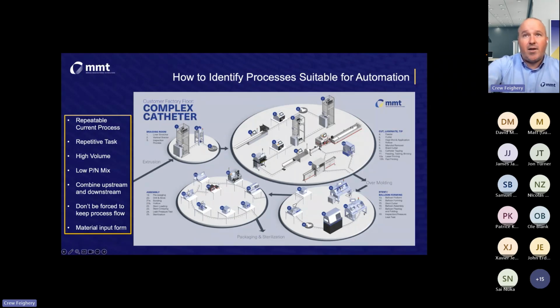You need to remove the mandrels, so you're going to pull those out. You're going to cut that braided catheter to length. Now you need to bond on the soft tip with an RF bonding system. And then once you've done that, you really would like to test the jacket to make sure that you don't have any exposed braids, whether when you do the reflow process it squeezed down too hard and left a thin spot in the Pebax jacket and then caused an exposed braid, or in the area where the bond goes from braided to non-braided, to make sure that one of those wires didn't flare out on you and come through the surface.